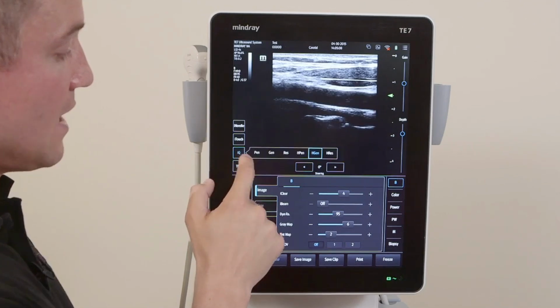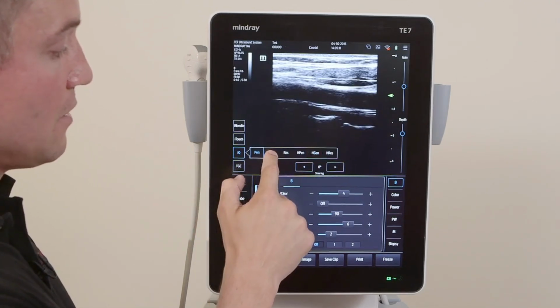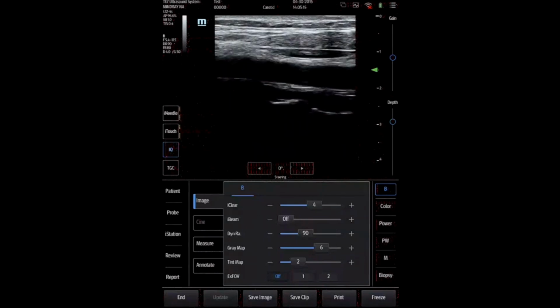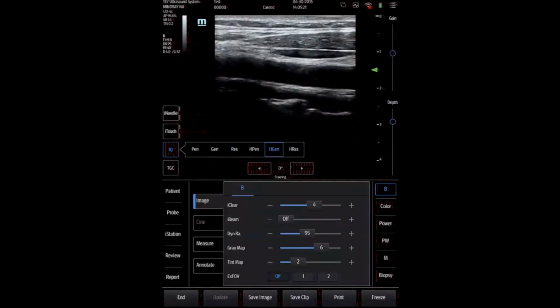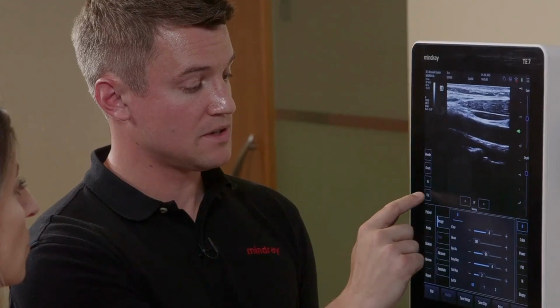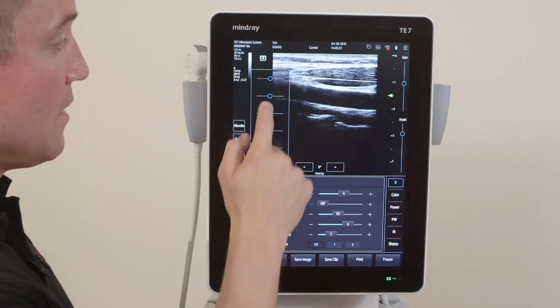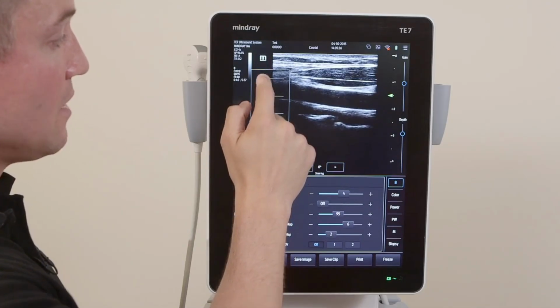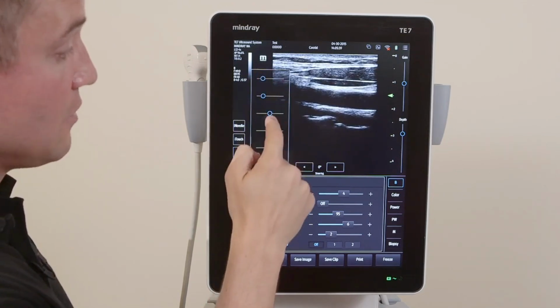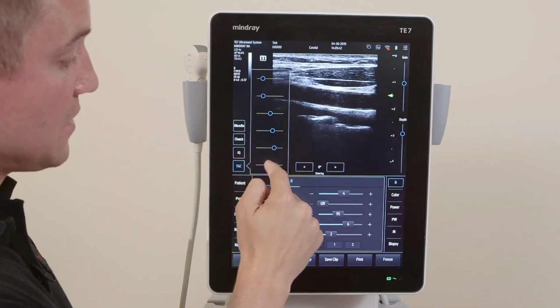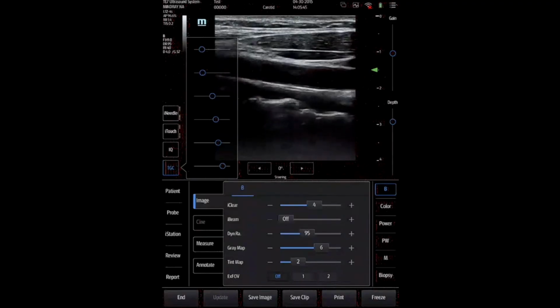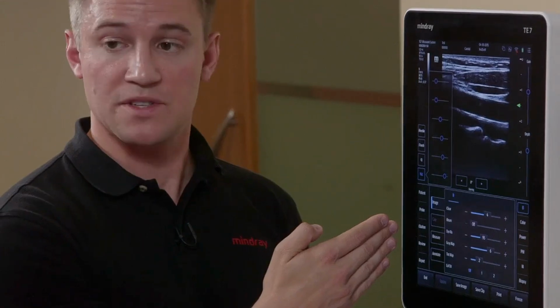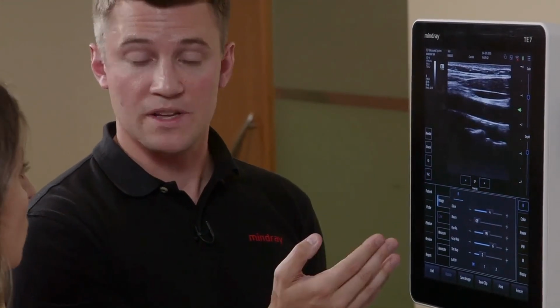Next, we have image quality. The IQ will allow you to change your frequency of your transducer. And we have 6 to 7 different settings depending on which transducer you're in. And you can see that with the H in front of the frequency, that will tell you that harmonics is on or you're in a fundamental frequency. I'll go ahead and deselect IQ and go to TGC, which stands for time gain compensation. This allows you to change your gain in one section of your image. So the top being the near field or the skin level, and you can go deeper down into your image, and I'll just increase these as we go deeper. If I don't touch the button again, the option will go away after about 6 or 7 seconds, or I can press the button and it'll go away as well.